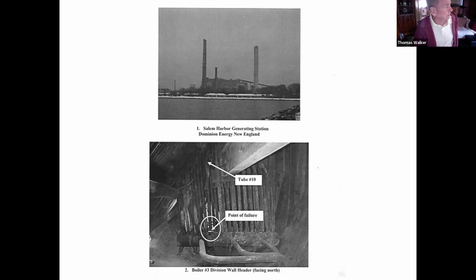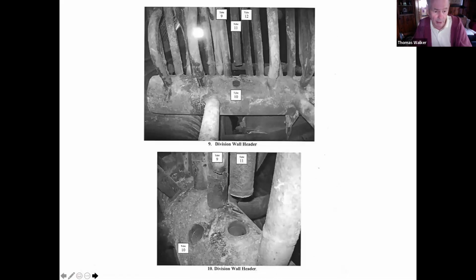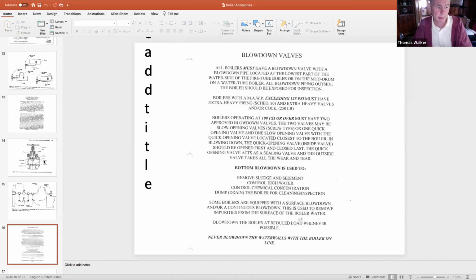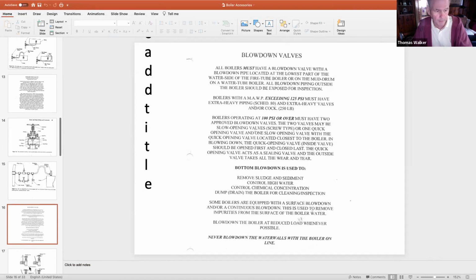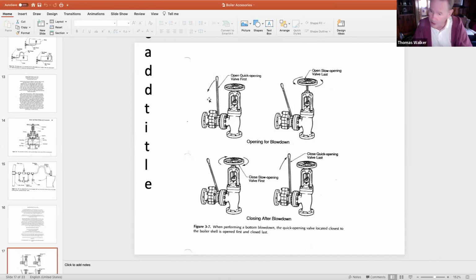And again, if the inspector's going to beat you up on this, he knows that you're kind of green and you haven't been around a lot of boilers. So I don't think they would typically beat you up on that. But that's a good question. That's a legitimate question. We'll talk about the sequence in a minute, but basically the valve sequence is you're going to open the inside valve, open the outside valve fully wide and close it. And then you're going to close the inside valve. There's a couple other steps, but that's the sequence of the valves.